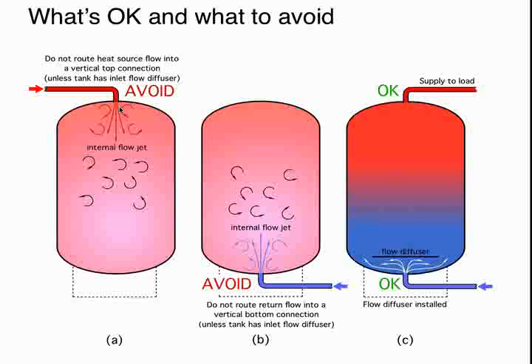And here's just another slide that kind of shows that. We want to stay away from topside vertical inlets that create a downward jet. We want to stay away from bottom side vertical inlets that create a jet. Now, over here I'm showing a stratified tank, and you notice one of the internal details that has helped create that: we still have this bottom inlet connection, but we've put some type of flow diffuser in there. And there's a lot of different potential designs. This shows a plate that has been welded into that tank, and there's an annular space out here. The basic idea is the incoming flow would impinge on that plate and spread out to the side, and depending on the space that we have out here, we would have a greatly reduced vertical flow velocity as that flow finally moves up into the volume of the tank.